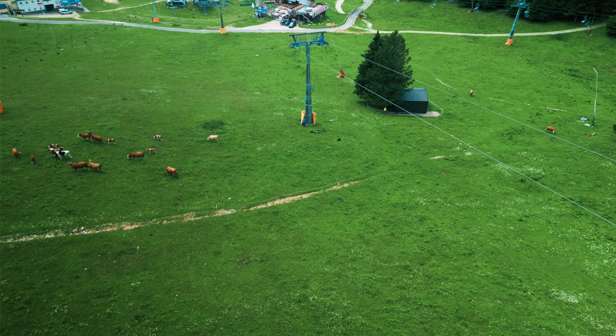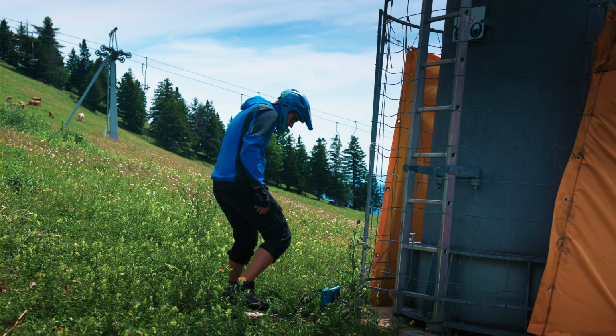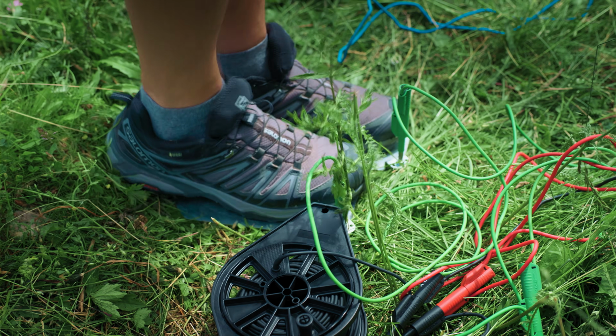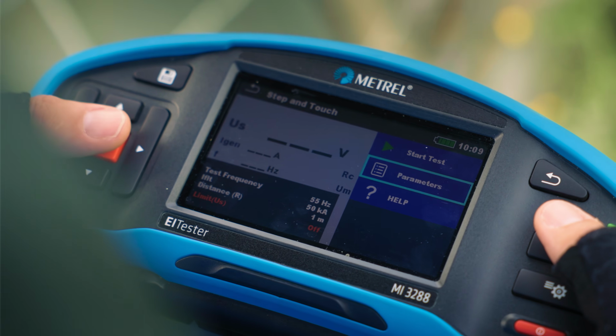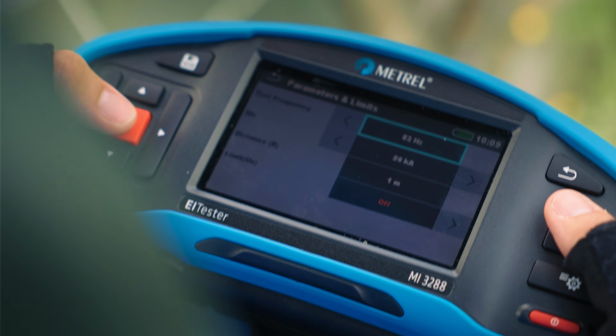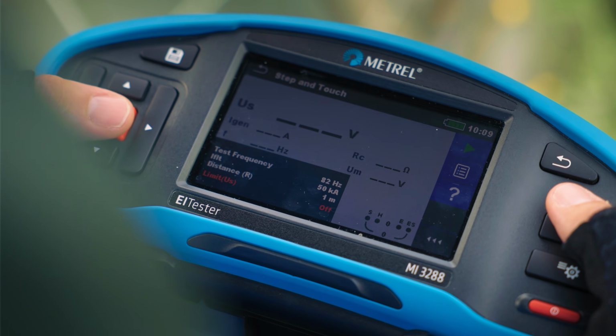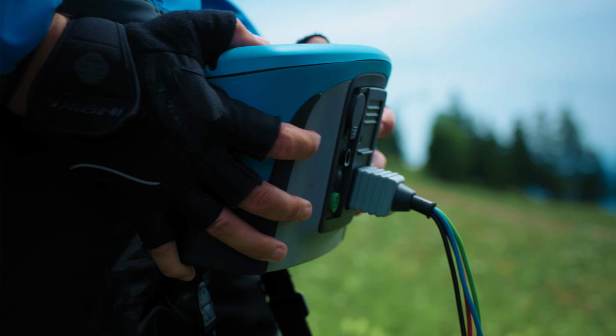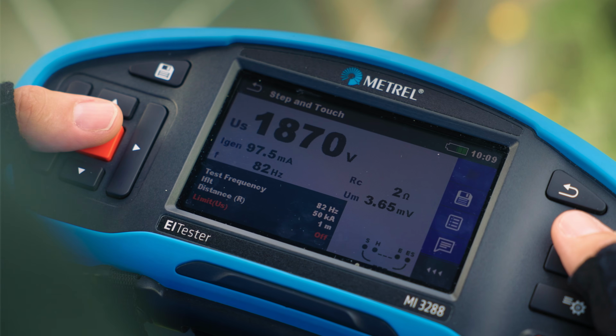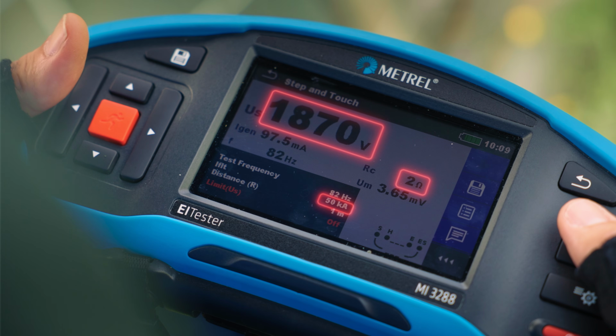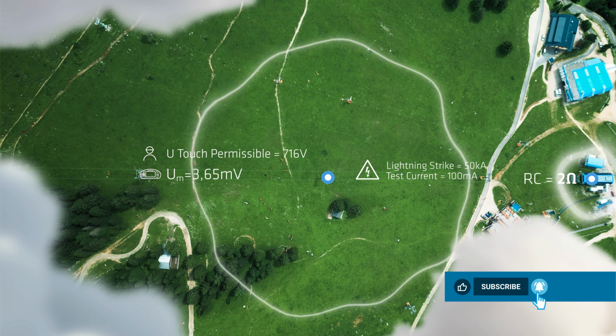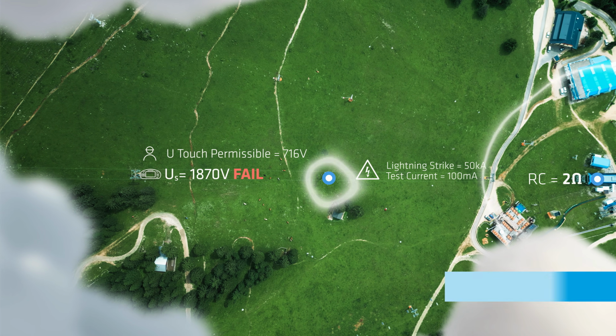Step on the parallel connected plates and start measuring touch voltage while generating a test current between the tower and the remote grounding. Before starting the measurement, ensure that the fault current is set to a minimum of 50 kiloamps. Every measured touch voltage higher than 716 volts represents a dangerous situation and requires appropriate reporting and repair. From the instrument screen, we can read many other important sub-results, including the resistance RC, where 2 ohms represents the remote grounding of the lower station.